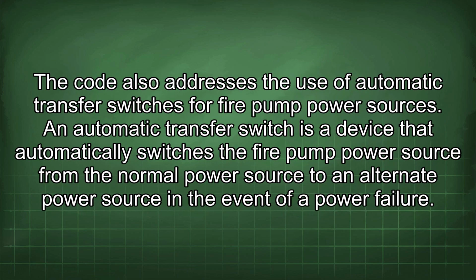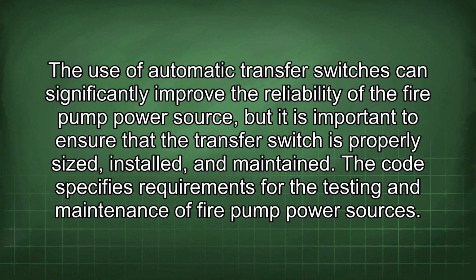The code also addresses the use of automatic transfer switches for fire pump power sources. An automatic transfer switch is a device that automatically switches the fire pump power source from the normal power source to an alternate power source in the event of a power failure. The use of automatic transfer switches can significantly improve the reliability of the fire pump power source, but it is important to ensure that the transfer switch is properly sized, installed, and maintained.